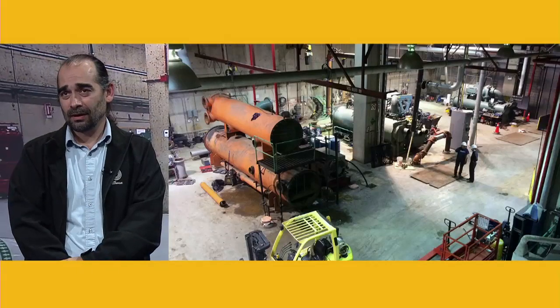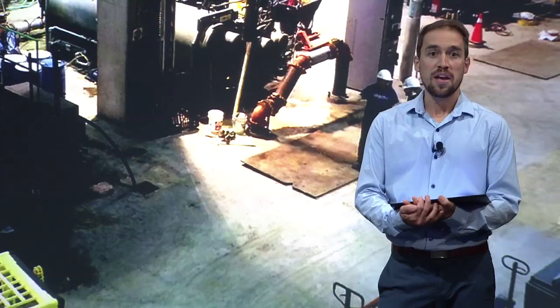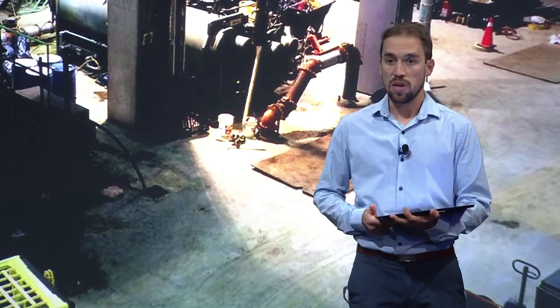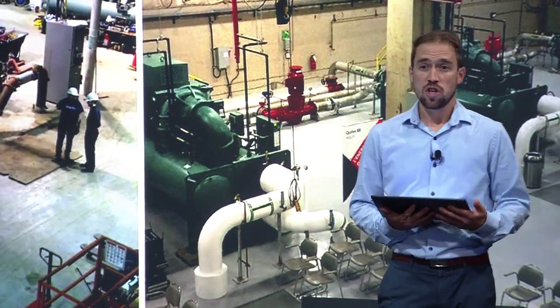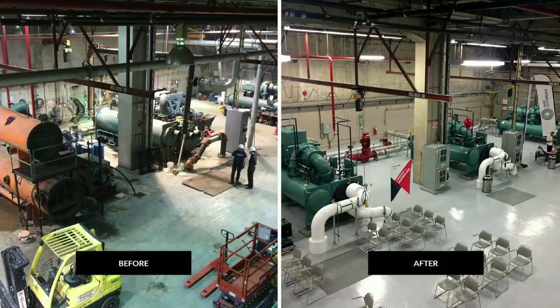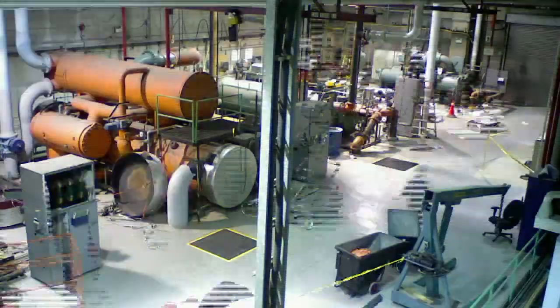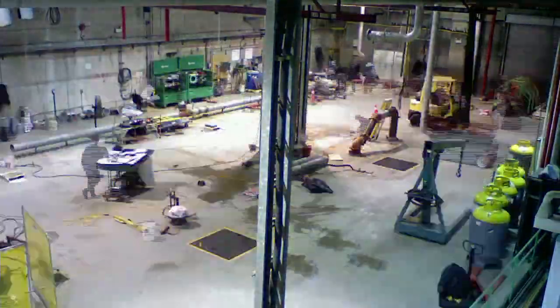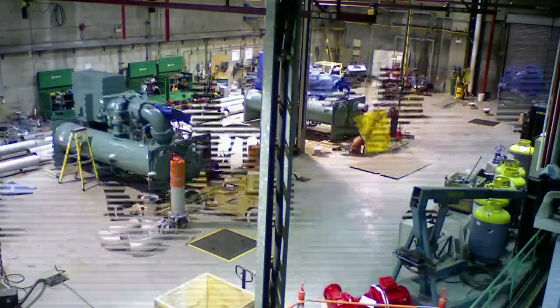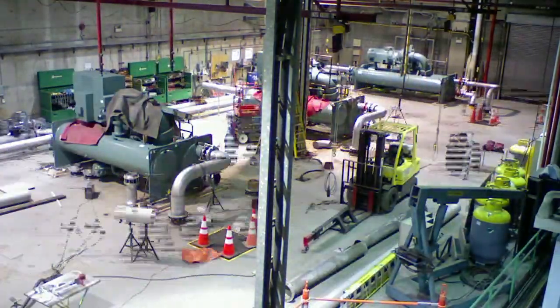Right, so you were not looking for an in-kind replacement here. Simon, there are a few things you want to add about the design you proposed and worked on with Dominic. Yeah, it was clear from the beginning that it wasn't just a one-for-one replacement. We needed to rethink the whole thing, not just to be flexible for all the events, but also to increase efficiency, make savings, and reduce operational cost because we wanted to reduce maintenance. So we had to carefully select the number and capacity of each chiller to make sure we could meet all these requirements.